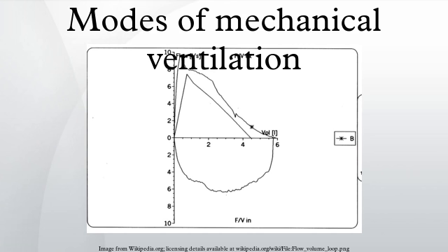Mandatory minute ventilation. Mandatory minute ventilation allows spontaneous breathing with automatic adjustments of mandatory ventilation to meet the patient's preset minimum minute volume requirement. If the patient maintains the minute volume settings for VT times F, no mandatory breaths are delivered.